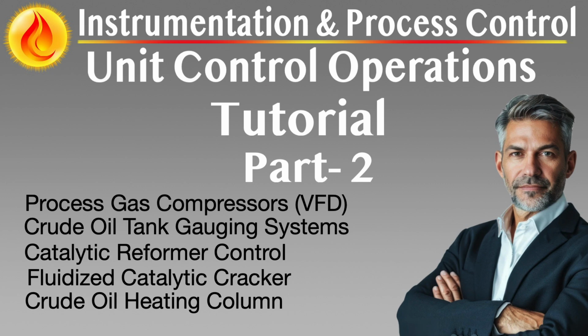Reflux control is another key component. Fixed or ratio-based reflux control can result in instability during feed or pressure swings. Modern columns use level-to-reflux cascade control or temperature-compensated reflux ratio adjustments to respond dynamically to load changes. Variable frequency drive, VFD, driven reflux pumps allow fine control of flow rate without inducing surge conditions. The system monitors overhead condenser duty and adjusts reflux accordingly to maintain internal column hydraulics within stable operating limits.